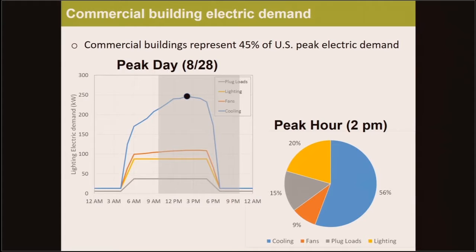On the left, we see a plot of the electric demand by end use on the peak day, which in this example is August 28th. It's very hot out and the sun is out as well. The plug loads and lighting demand pick up when people arrive in the morning, then the HVAC end uses ramp up as the day gets hotter and decline in the evening. On the right, we can see that at the peak hour of 2 p.m., nearly two-thirds of this demand is from HVAC, namely cooling and fans. However, one-fifth of the peak demand is from lighting. This breakdown would vary significantly by climate and building type, but lighting is a sizable component of peak demand.